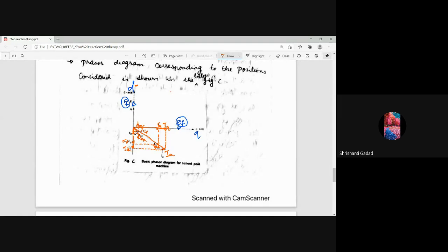Yes, sir. This ψ_AR flux, because of the armature winding, is very close to the direct axis. The reason is very simple: the direct axis is characterized by the lowest reluctance path. So always, flux chooses what? The lowest reluctance path, that is ψ_d. So it will be very close to ψ_d.